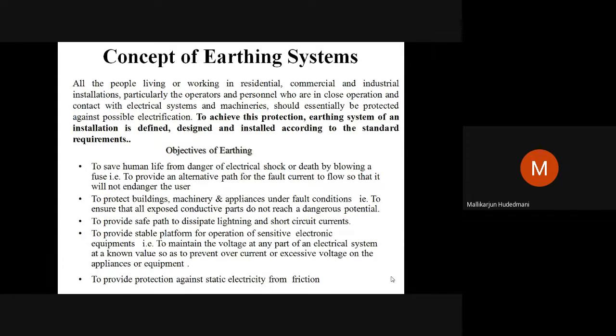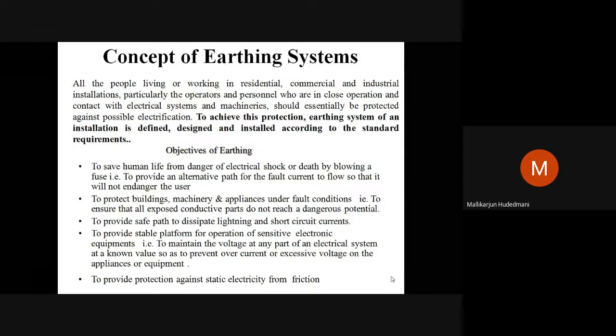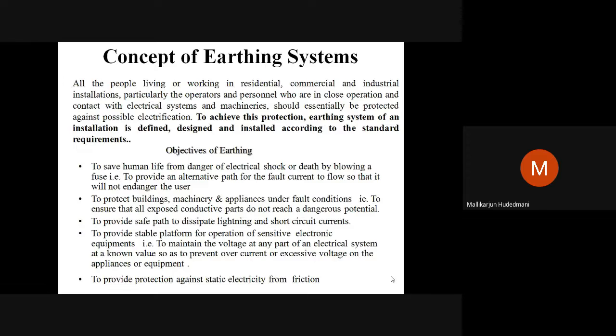It provides a safe path to dissipate lightning and short circuit current. It absorbs the higher fault current and any lightning strikes that occur, and takes them down to the earth point. And it provides a stable platform for operation of sensitive electronics. It means electronic devices, laptops, mobile phones, tabs, or any sensitive electronic circuits are very critical. Whenever there is a fluctuation or any high rush of current, they start malfunctioning and may get damaged. For them, earthing is very, very necessary. So these are the points we need to take care of.